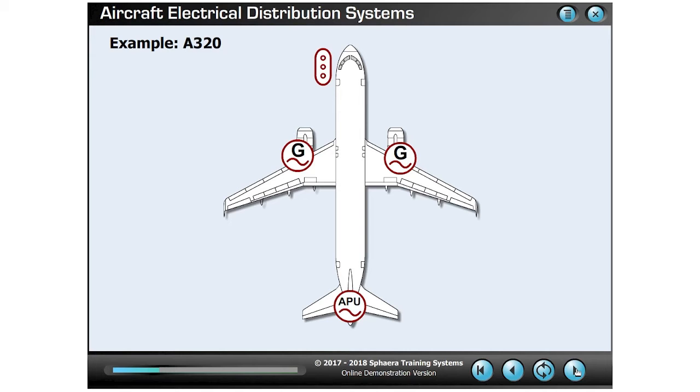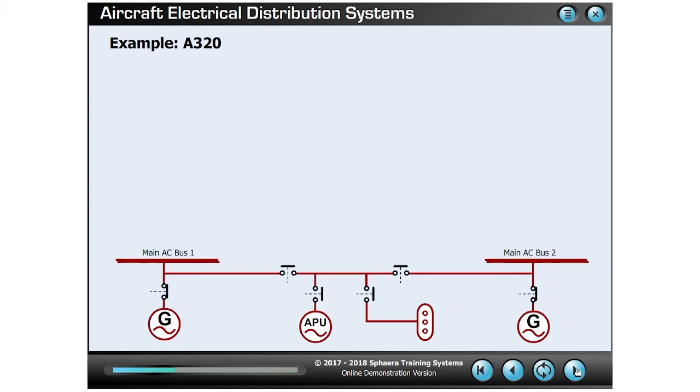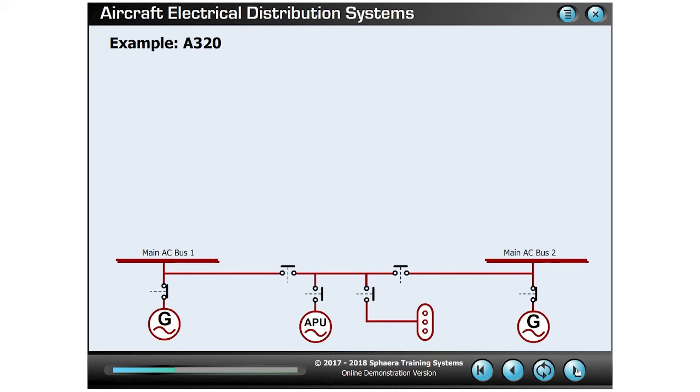If we now switch to a schematic view, we see that each of these power sources can be interconnected by a system of generator control breakers and bus tie breakers. This means that any of the four power sources can provide power to any of the two main AC busbars.